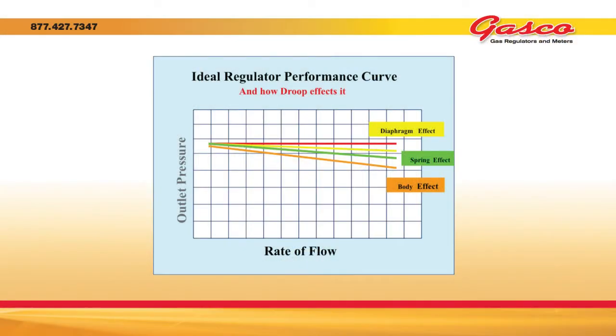If a manufacturer could construct an ideal regulator, the performance curve would look like a straight line curve. An ideal regulator would not be affected by the mechanics of the regulator. The horizontal axis at the bottom of the graph shows the rate of flow, and the vertical axis shows the outlet pressure. As the rate of flow increases, the outlet pressure would not change.